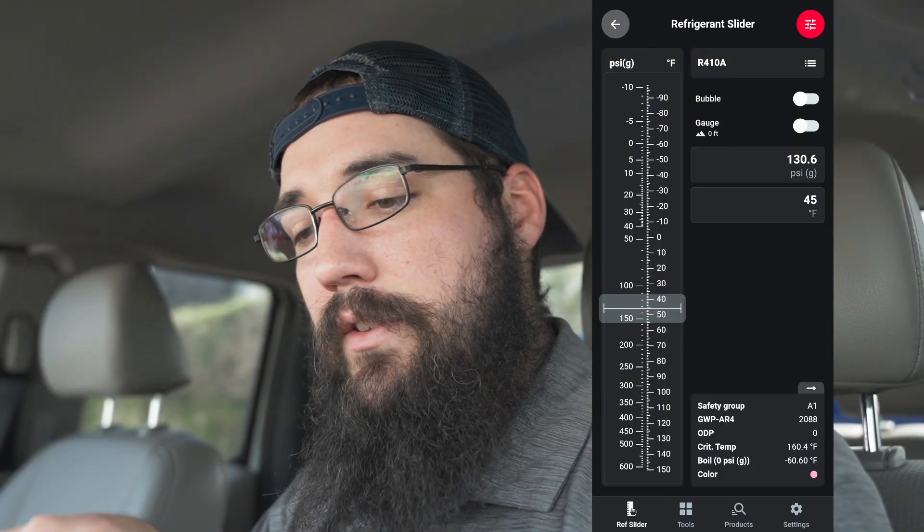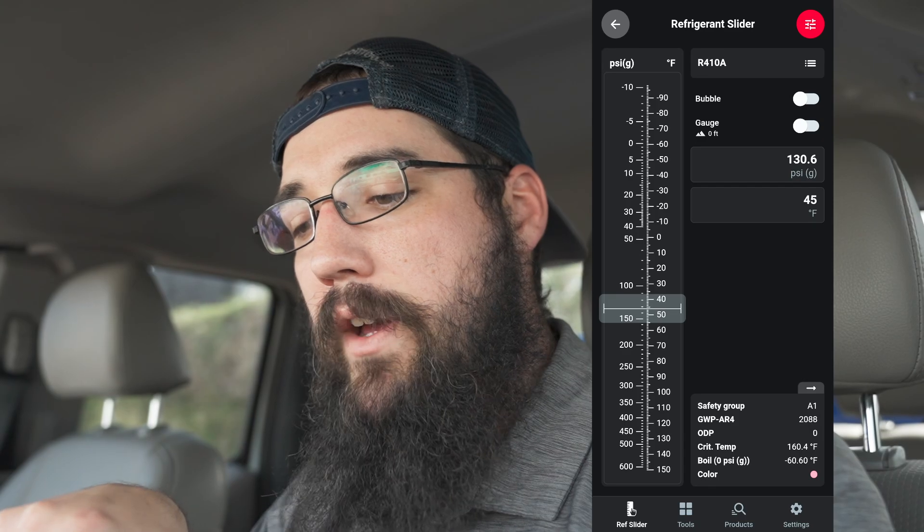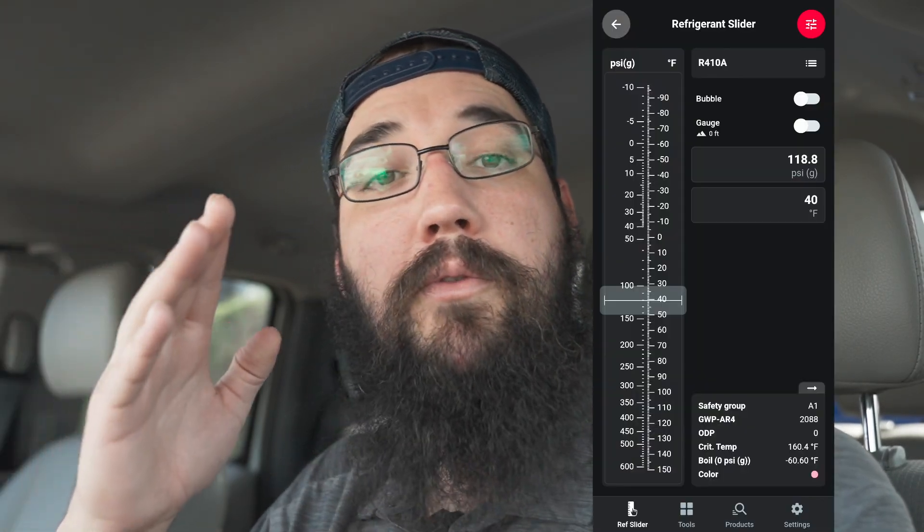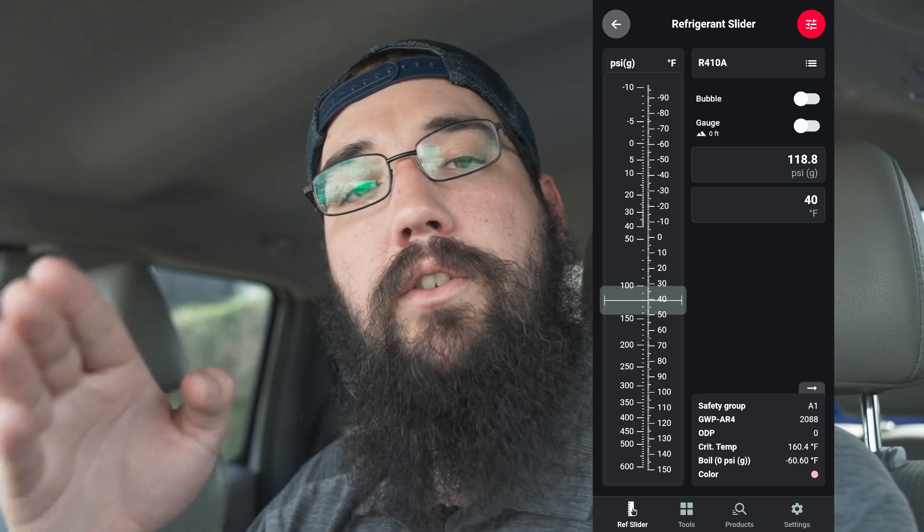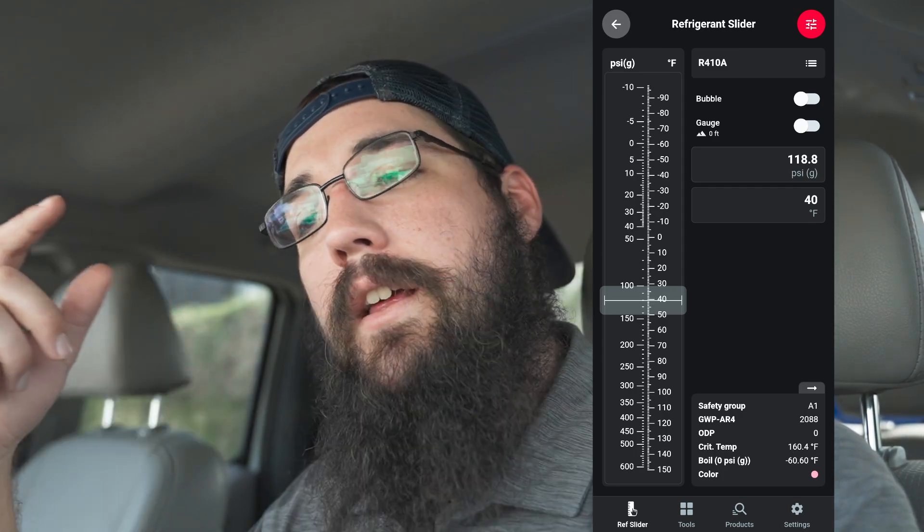At 40 degrees saturation that's 118 PSI on the gauge for 410A. If I add 5 degrees to get to 45 degrees saturation, that puts me at 130 PSI. So setting a 5 PSI dead band around that — by the time I get to a load of say 75-degree return air, I'd have room to stage up the circuit the way I want to.